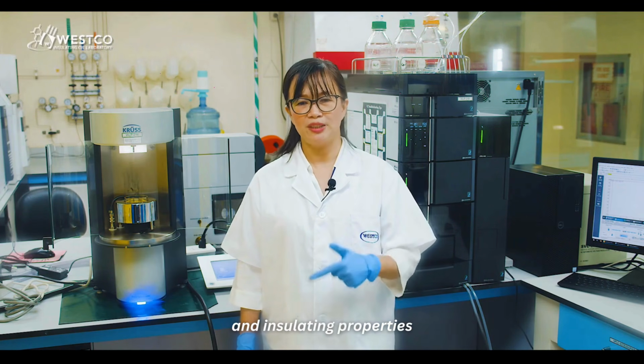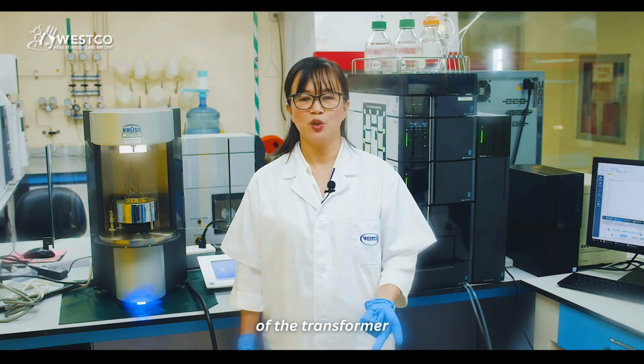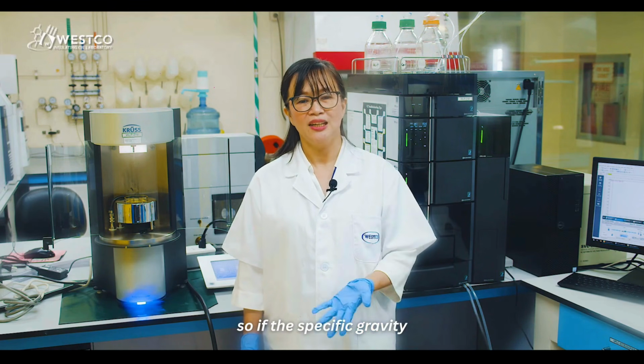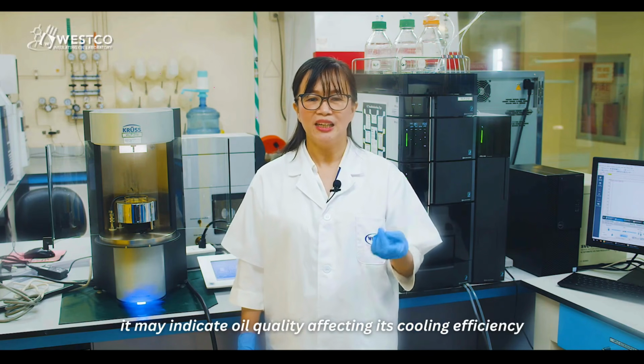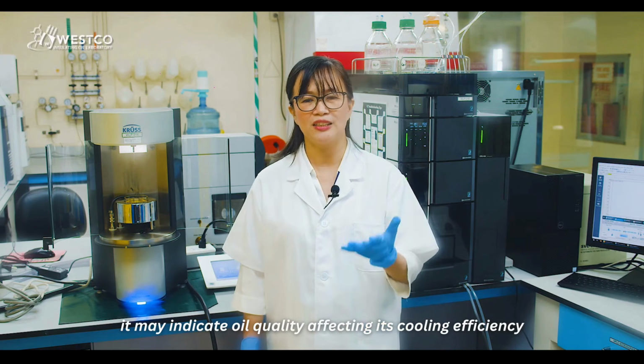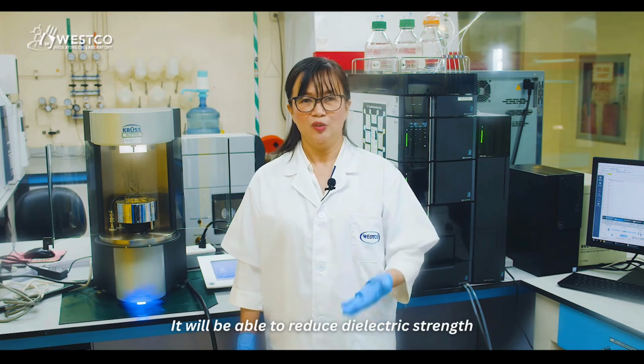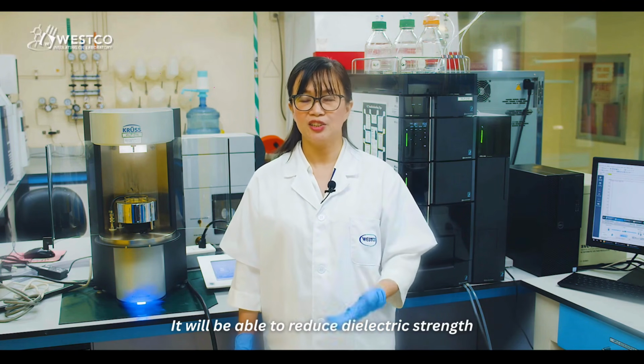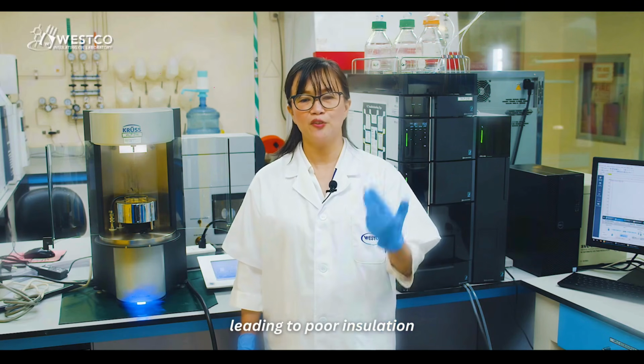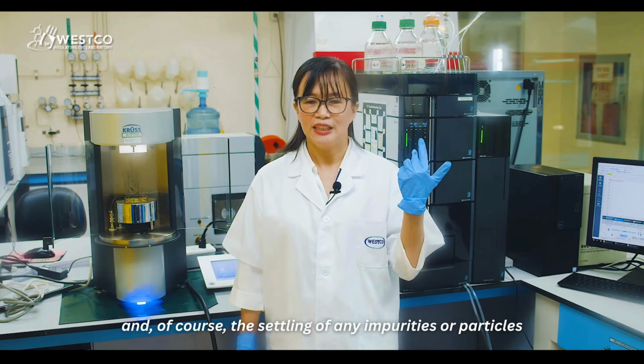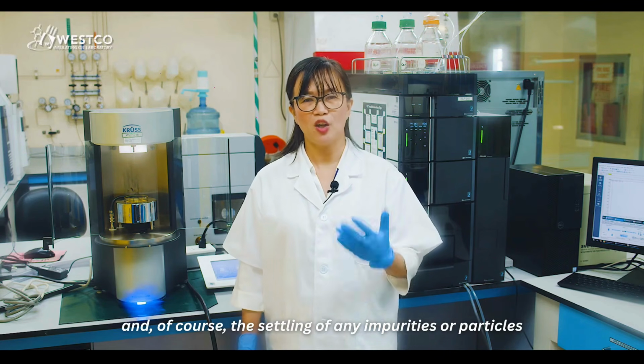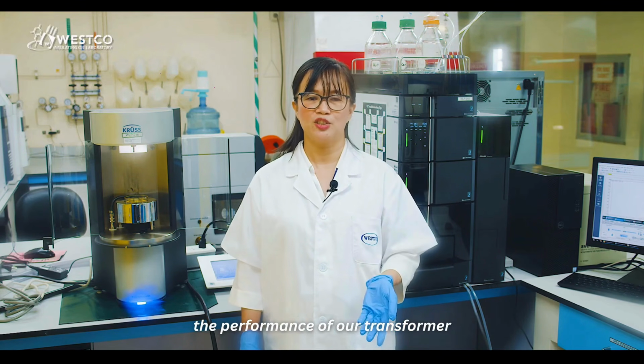Next one is of course to check the performance of our transformer, because specific gravity affects its cooling and insulating properties. So if the specific gravity is outside the normal range, it may indicate poor oil quality, affecting its cooling efficiency. It can reduce the dielectric strength, leading to poor insulation, and of course the settling of any impurities or particulates which can compromise the performance of our transformer.